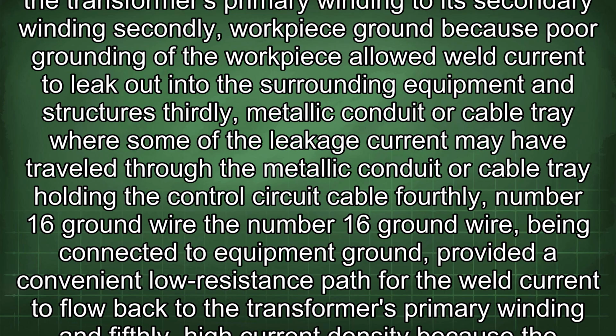Thirdly, metallic conduit or cable tray, where some of the leakage current may have traveled through the metallic conduit or cable tray holding the control circuit cable. Fourthly, number 16 ground wire. The number 16 ground wire, being connected to equipment ground, provided a convenient low resistance path for the weld current to flow back to the transformer's primary winding.